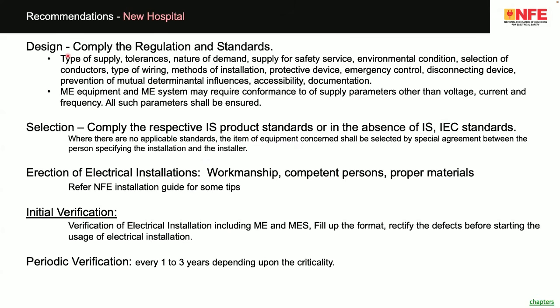Then once you design the electrical installation, the consultant who is designing has to 100% comply with the regulation and standard. All the list of items is given here, starting with the type of supply, tolerance, nature of demand, and so on. I don't want to read it. Select the electrical equipment which is in compliance with the IS standards, and in the absence of an IS standard, IEC standards can be used. Erection and installation: here workmanship, competent person, proper material.